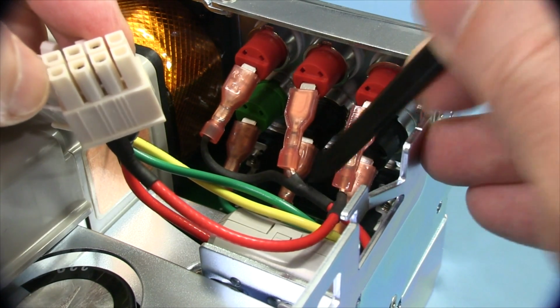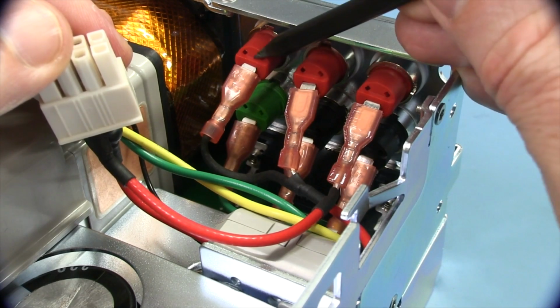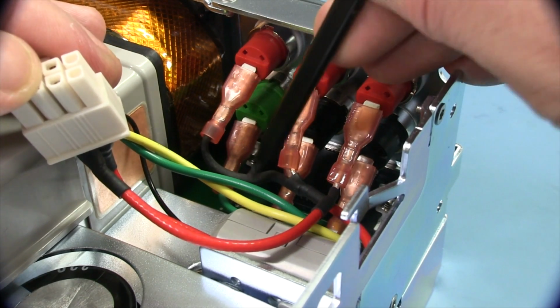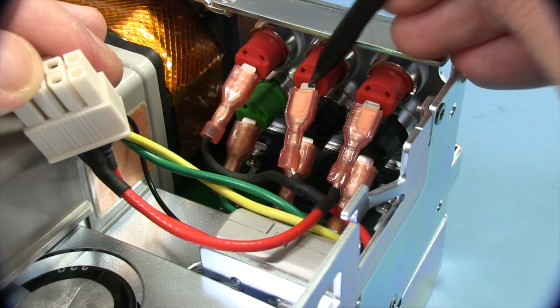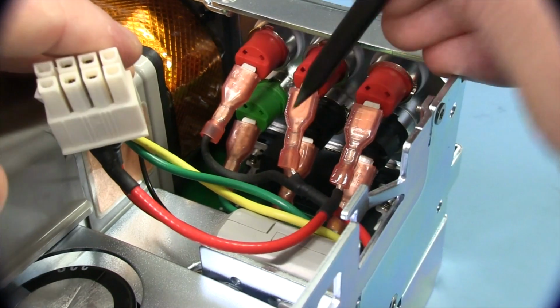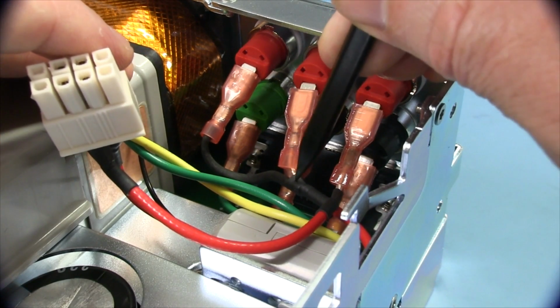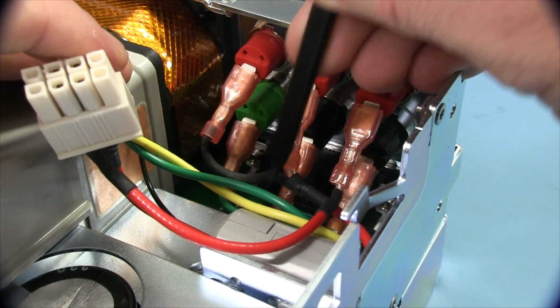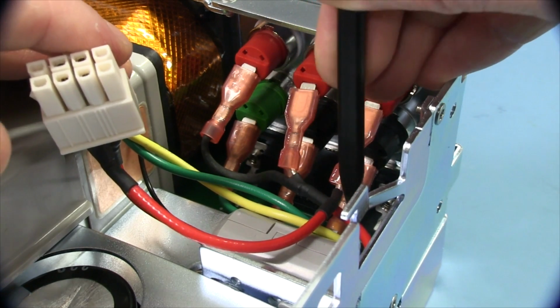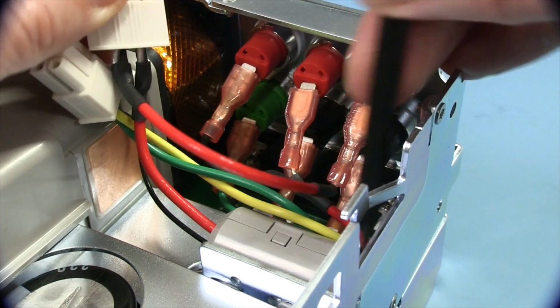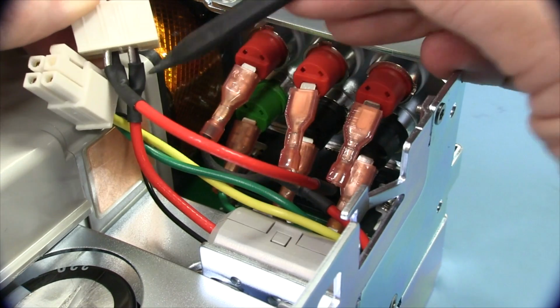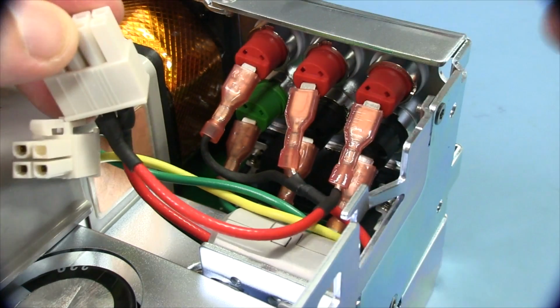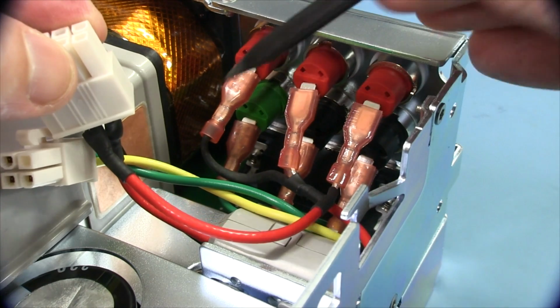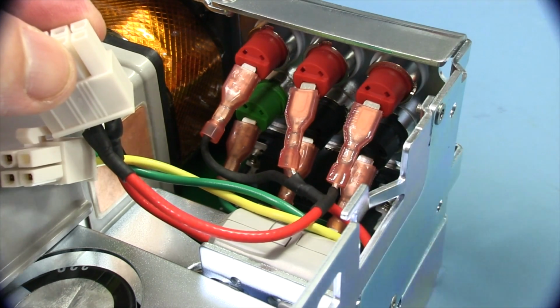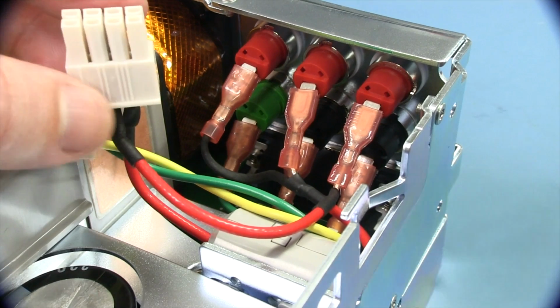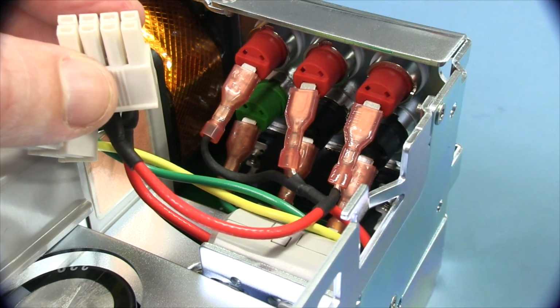So you can see the guard terminal here, that's actually connected through to the force line. Yeah, that is the force line there. So the guard terminal is actually connected to the shield of the coax. Then that goes through that ferrite clamp up into here like that. So that's what the guard terminal does, and then you can extend that guard terminal further out on the other side with your triaxial leads.